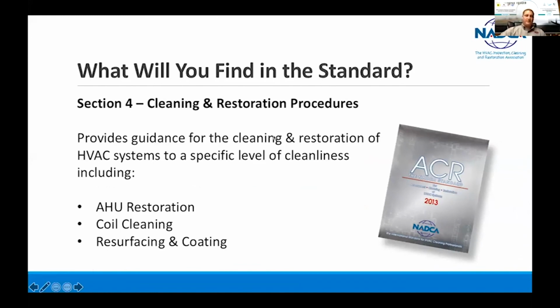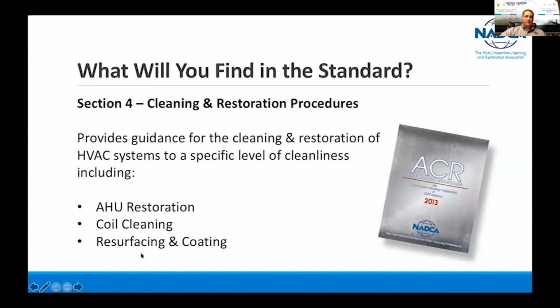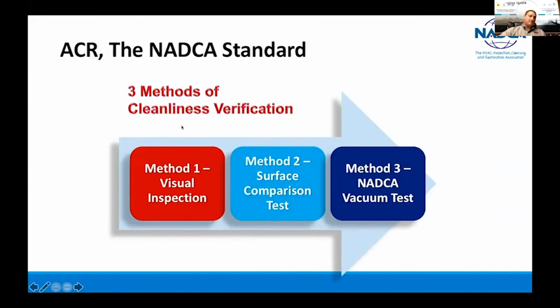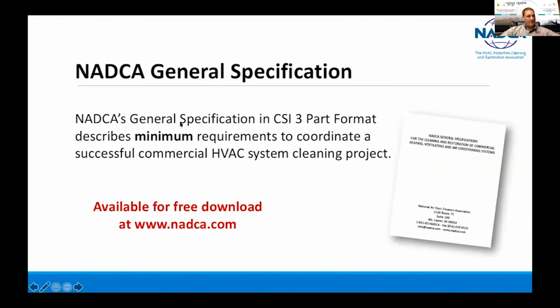Provides guidance for the cleaning and restoration of HVAC systems to a specific level of cleanliness, including air handling unit restoration, coil cleaning, resurfacing and coating. And there are three methods of cleanliness verification. The first one is just visual, what you see. Does it look dirty? Method two, surface comparison test. And method three, the NADCA vacuum test. NADCA's general specification in CSI 3 part format describes minimum requirements to coordinate a successful commercial HVAC system cleaning project. This is another free download that you can get at NADCA.com.